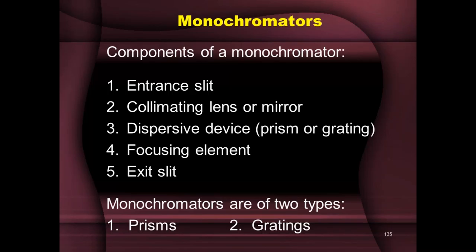So we have two slits — entrance slit and exit slit — and in between them, two lenses or mirrors. The collimating lens makes the radiation parallel before it hits the dispersive device, and then the parallel radiation coming out of the dispersive device is focused onto the exit slit. The main component is the dispersive device, which could be a prism or grating. Based on what is present, we say monochromators are of two types: prism-based or grating-based.